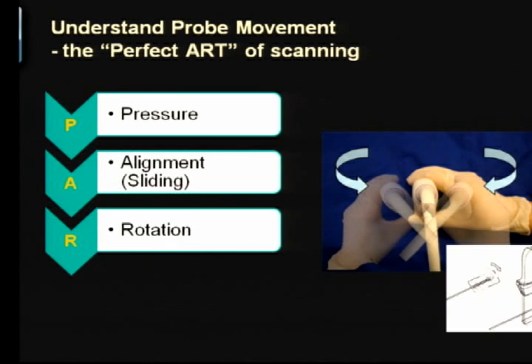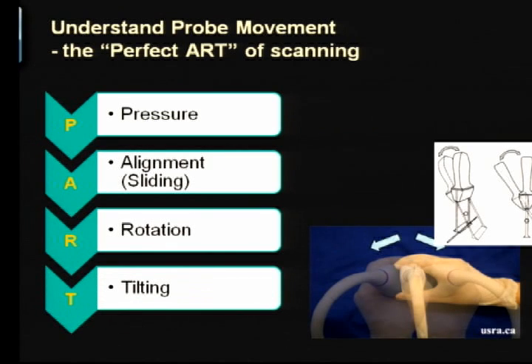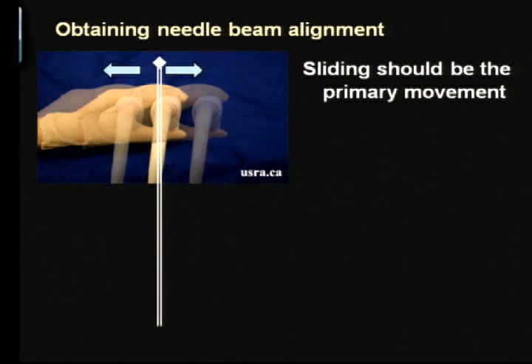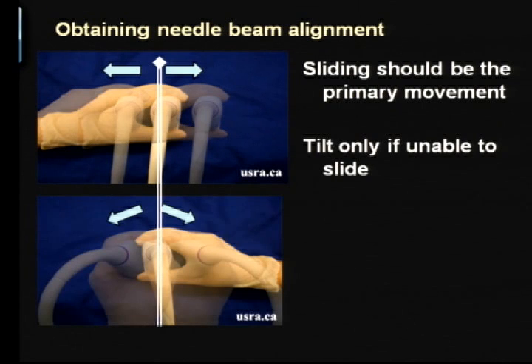You can also rotate the probe, and you can tilt the probe. But when we're talking about attaining alignment, as I've said before, sliding should really be the primary movement, and this is because you can make the smallest adjustments in beam position relative to the needle. You should resort to tilting only if you're unable to slide.